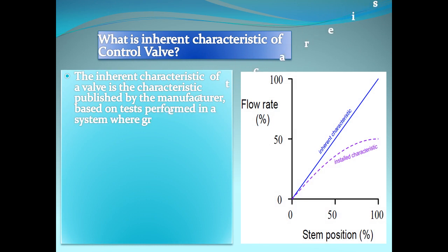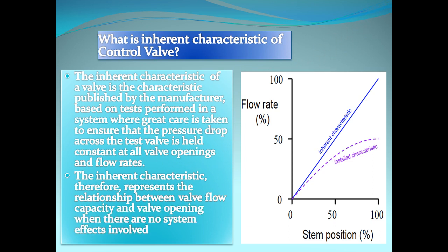What is inherent characteristic of control valve? The inherent characteristic of control valve is the characteristic published by the manufacturer based on tests performed in a system where great care is taken to ensure that the pressure drop across the test valve is held constant at all valve openings and flow rates. The inherent characteristic therefore represents the relationship between valve flow capacity and valve opening when there is no system effects involved. Here we have a graph. The blue line shows the inherent characteristic and purple line shows the installed characteristic.